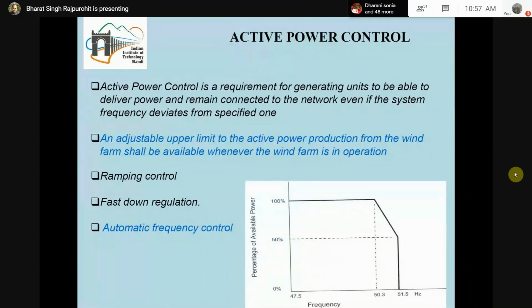The second one is known as fast down regulation. The meaning is that suddenly the grid is at an abnormal condition and we need to reduce the output from a wind farm, so this control ability should be available with the operator so that fast down regulation can be done. The next thing is that whatever active power output is coming from the wind farm should be controllable in such a manner that the set point of the wind farm in terms of active power can be changed as per the requirement of the grid.